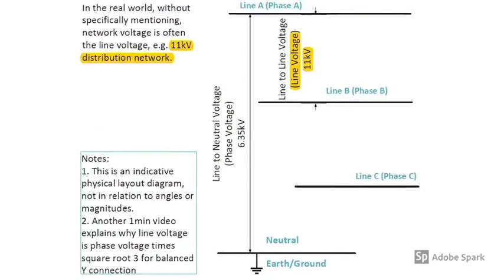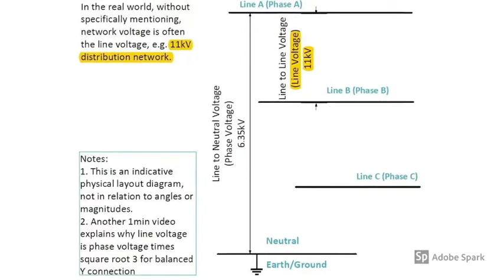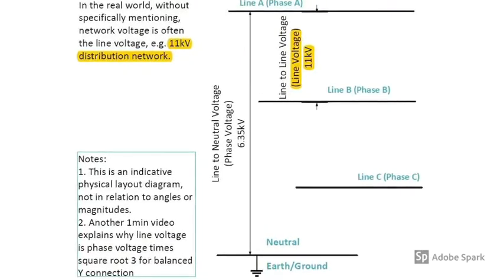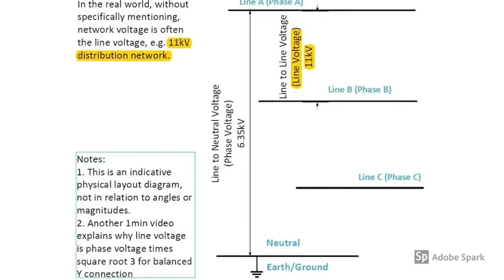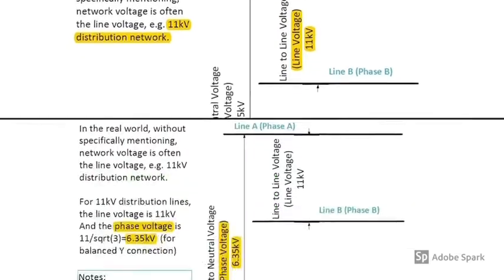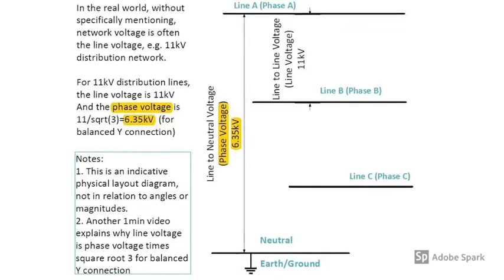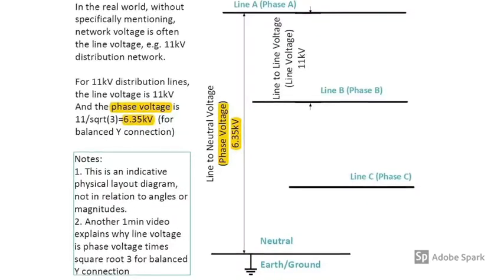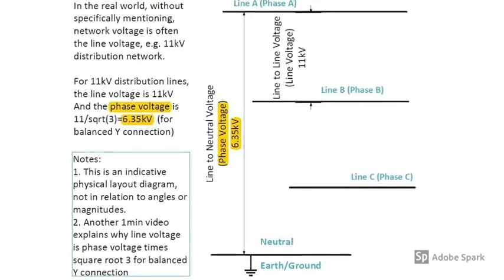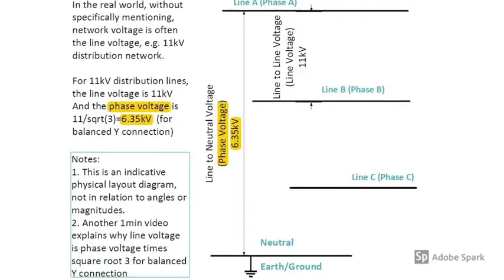In the real world, without specifically mentioning, network voltage is often the line voltage. For example, 11kV distribution network in southeast Queensland. The line voltage is 11kV, the phase voltage is 11 divided by square root 3, which is 6.35kV for balanced wye connection.